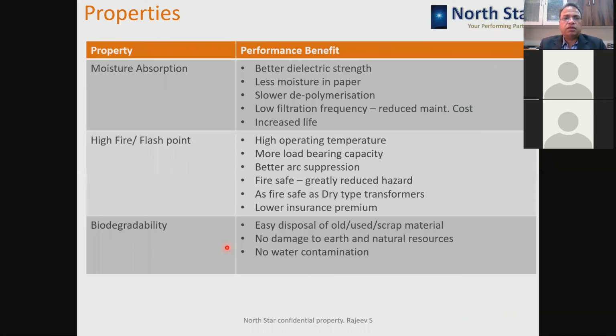Now coming to properties of esters. There are three major properties. One is moisture absorption capability, then higher fire and flash point, and biodegradability. And what are the advantages of these properties? Moisture absorption improves the dielectric strength, that is the property of withstanding higher electrical stress by the material. The moisture in the solid insulation will be less with the esters. Depolymerization is directly linked with the aging of the transformer, meaning how the transformer is getting older. With the esters, the depolymerization process slows down, so the life of the transformer will be much higher than with mineral oil.